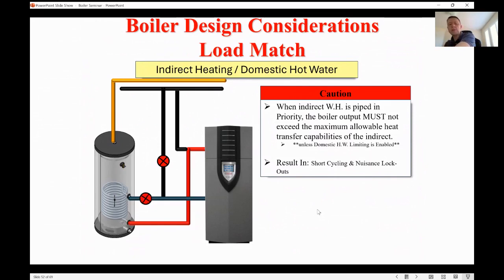Well, you can get into a cycling situation here as well. Let's say this is a 2 million BTU per hour boiler. It's handling the building, but they're just doing hand washing, right? It's just an office building. There's not a big domestic load. So let's say this indirect is sized so that basically it'll take about 500,000 BTUs on that coil, right?